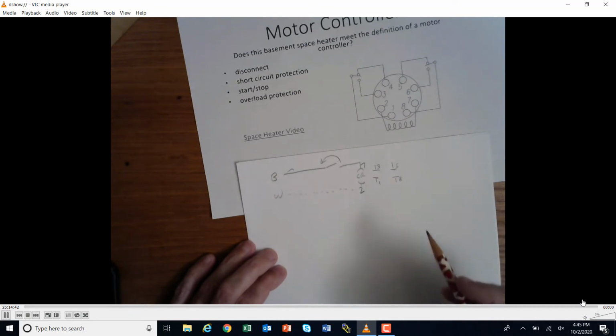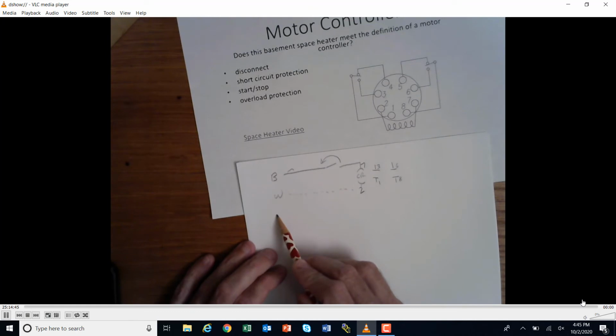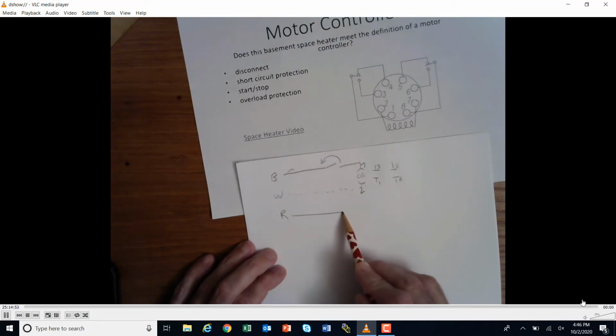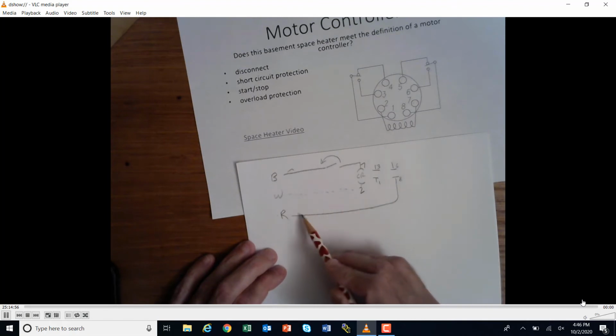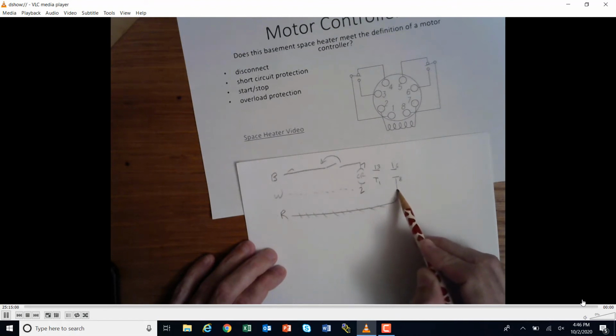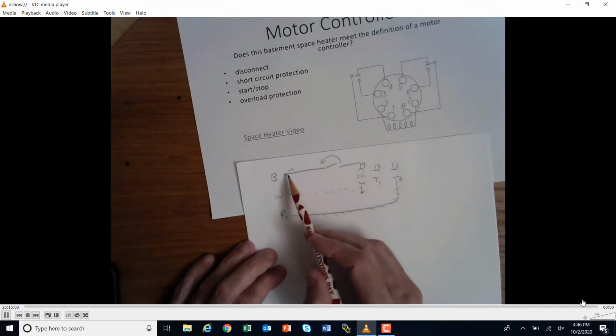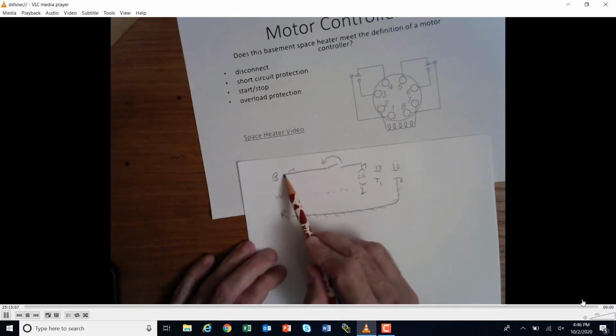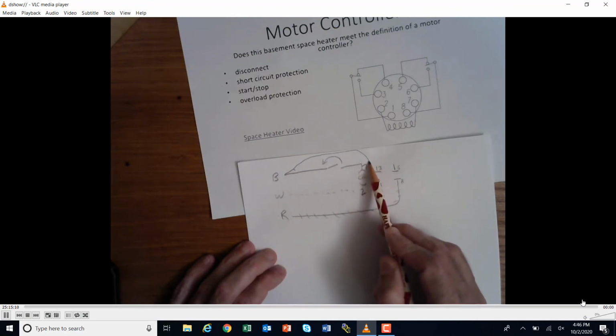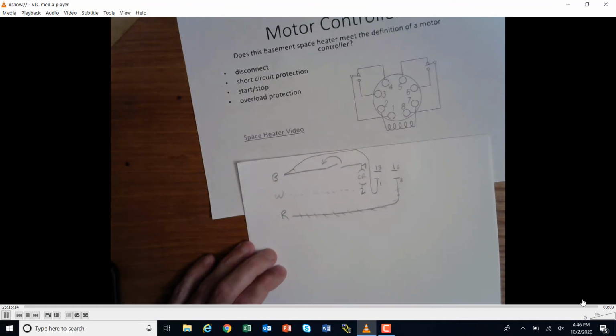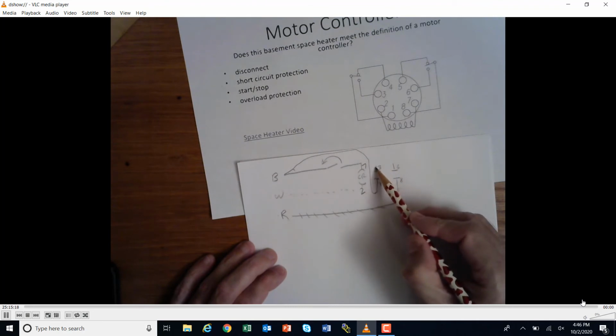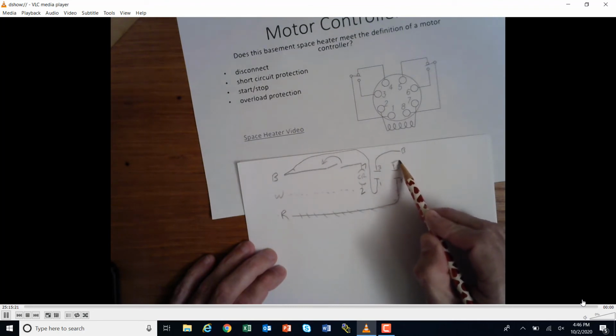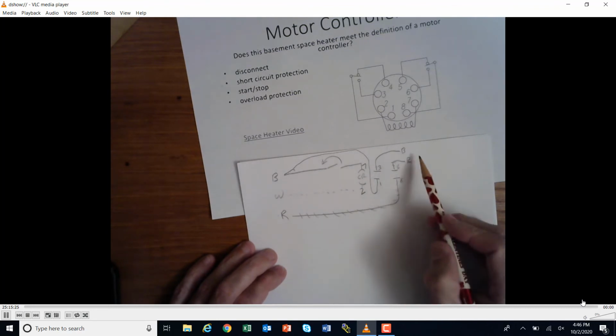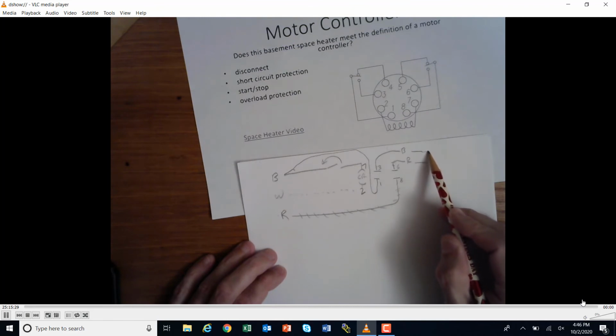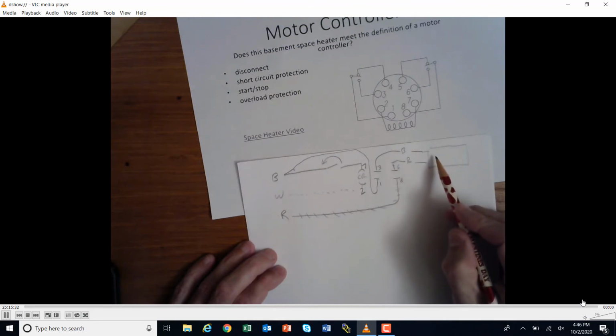Then what I did was I needed high voltage, so I had to use the red wire as well. I took one of the switches and switched through the red wire. Then the other switch, I had to pick off the black from my box again, so I ran a black wire to the other switch. So when that closed, on this side I had black and red, which was 240 volts right there.